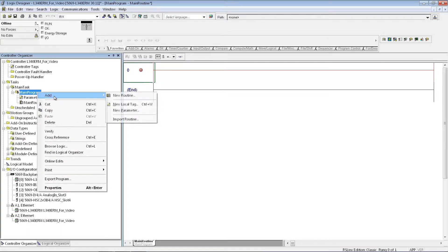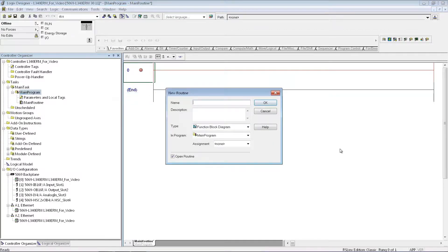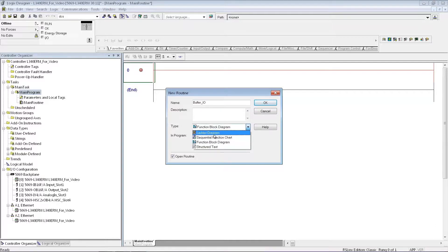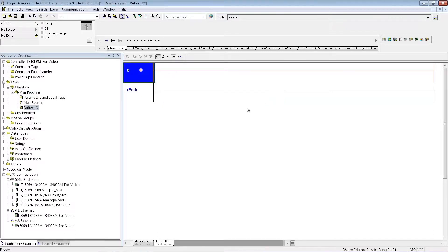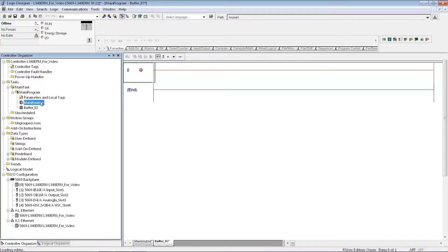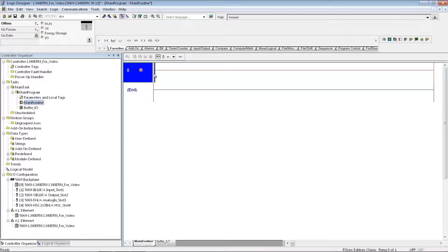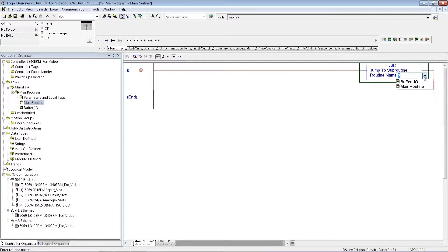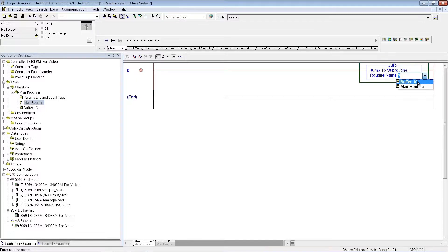Alright, before I jump to the subroutine, I need to make the subroutine, so I'll just call this Buffer.io, it's going to be a ladder program, say OK. Now I'll go back to my main routine, and the first thing I'm going to do is set up a jump to subroutine, and now I can select that subroutine. In this case, I'm just going to make a Buffer.io module, because ControlLogix, CompactLogix, they are asynchronous as far as the way they scan the I.O.